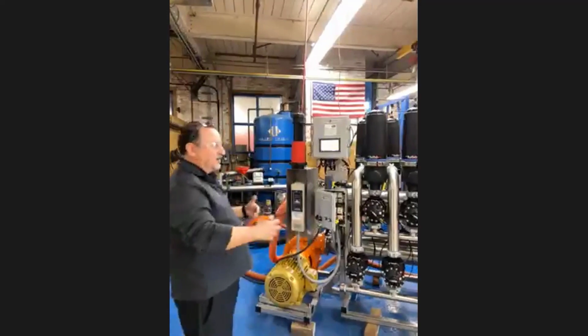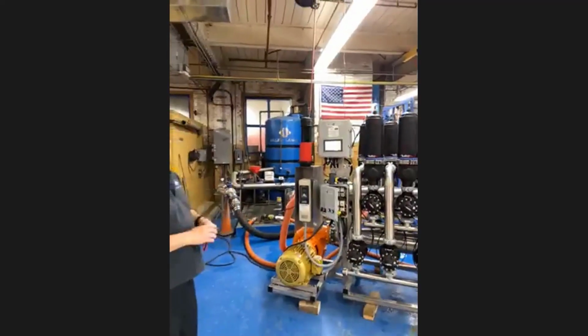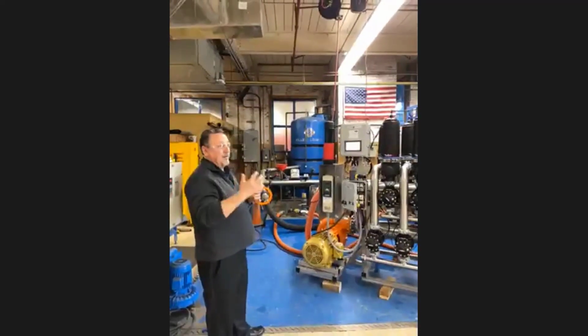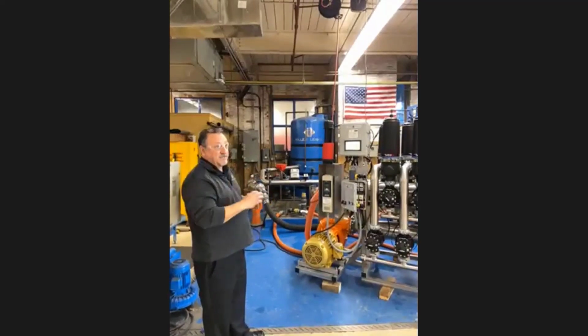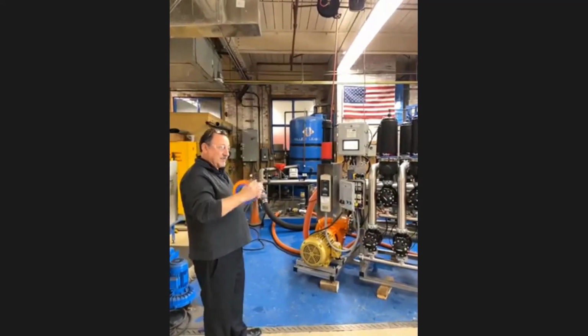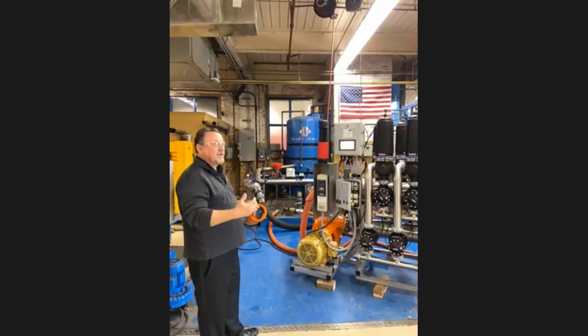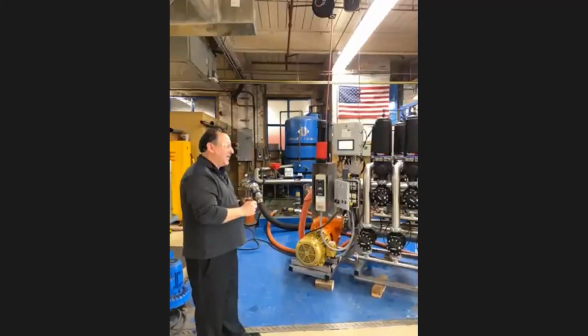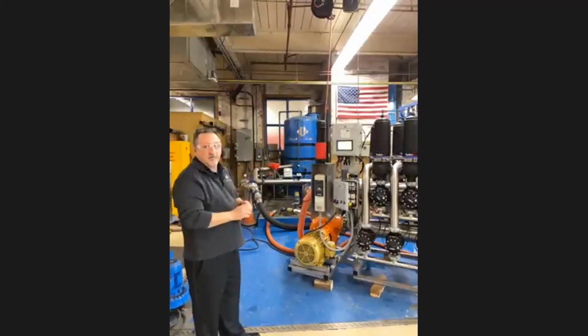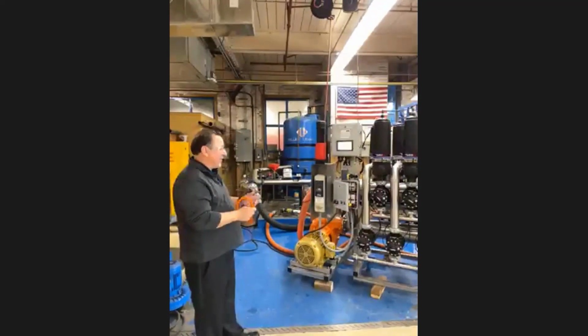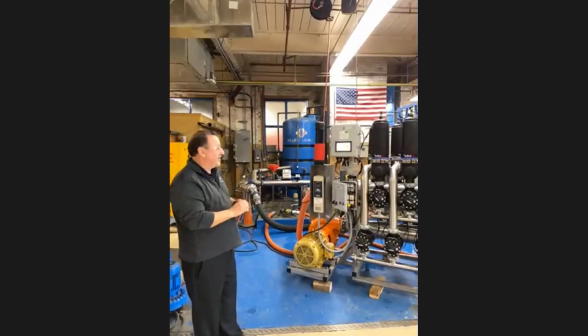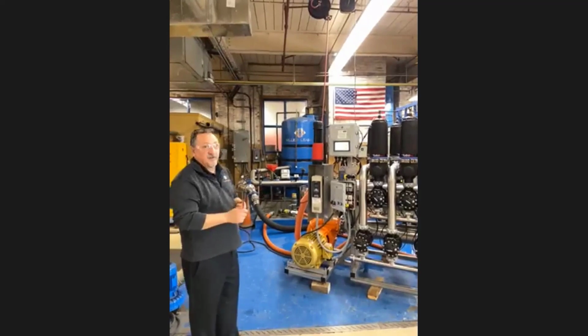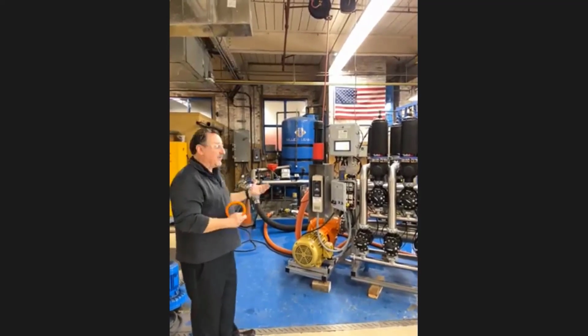It might be 800 or 900. Now that works out well when you have multiple towers, and maybe you want to shut off a few towers, because then you can hit different hertz levels for different flow rates for each tower. But most of the time they do not come with VFDs. This was requested by the customer to use the Yaskawa VFD. Our standard is Danfoss here, but they requested a Yaskawa.